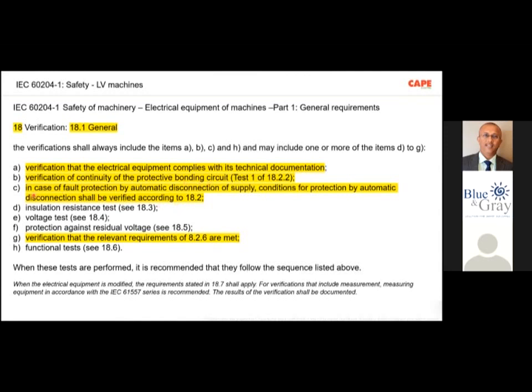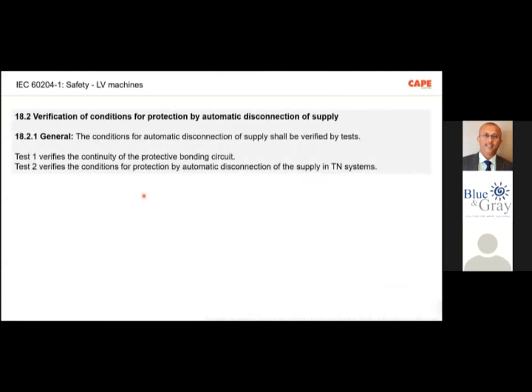And always the next test is, in case of fault protection by automatic disconnection of supply, the condition of protection by automatic disconnection of supply shall be verified. So these two tests, one is continuity of protective bonding circuit and the other is fault protection by automatic disconnection of supply. These two I will explain with videos for your information. Basically, every electrical item which you are connecting to your installation also needs to be tested. 18.2 is verification of condition of protection by automatic disconnection of supply. I will cover this a little bit later.